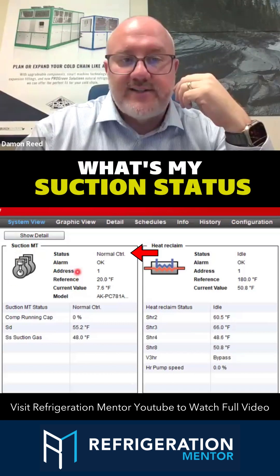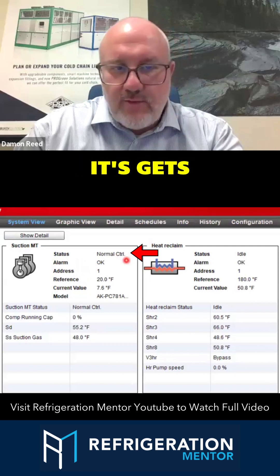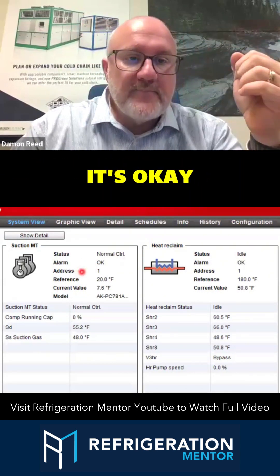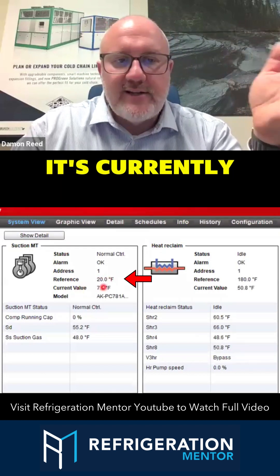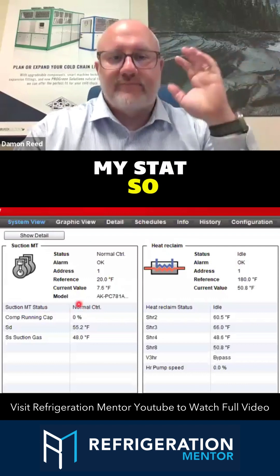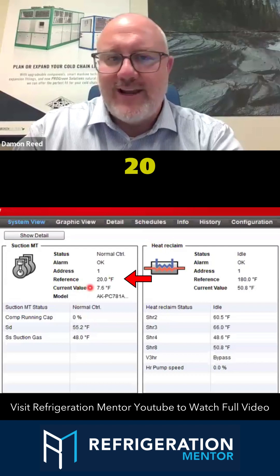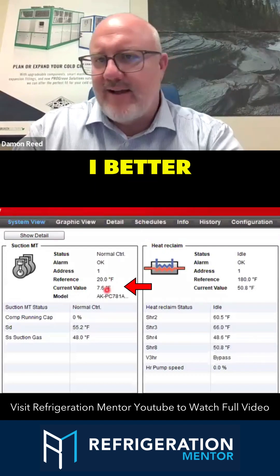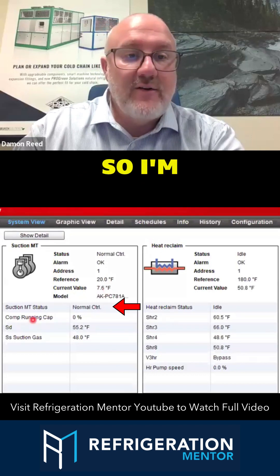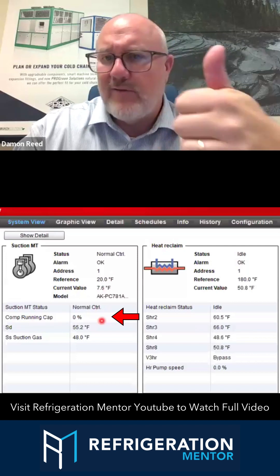You can see here what my suction status is. In this particular moment on this system, it's normal control, meaning there's no alarms — it's okay. I've got a 20 degree suction set point and it's currently at 7.6 degrees. Right away, before I go any further, if my reference point is 20 and I'm at 7.6, I better not be running any compressors. So I'm in a normal control status and my compressor running capacity is 0%. Perfect — that's what I expect.